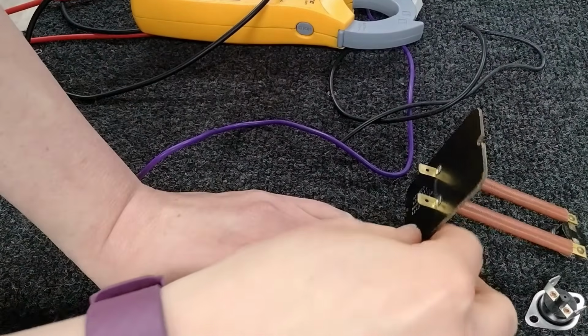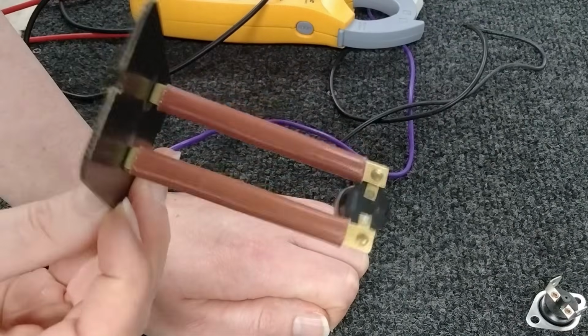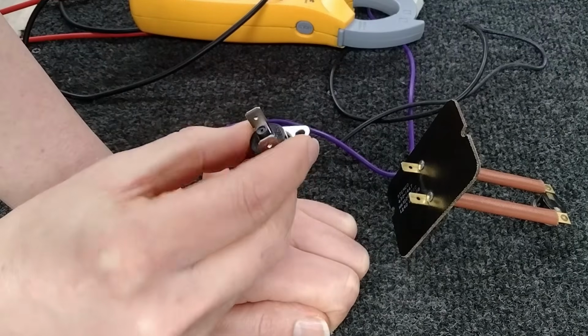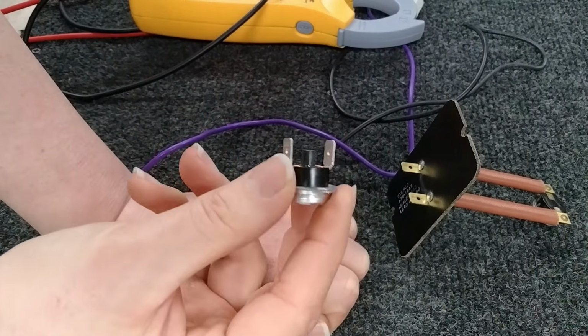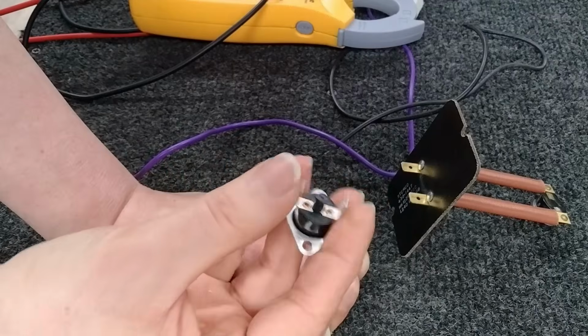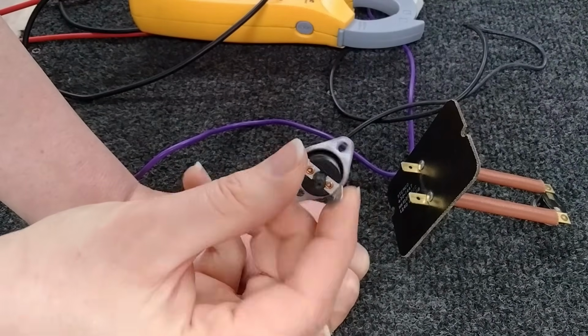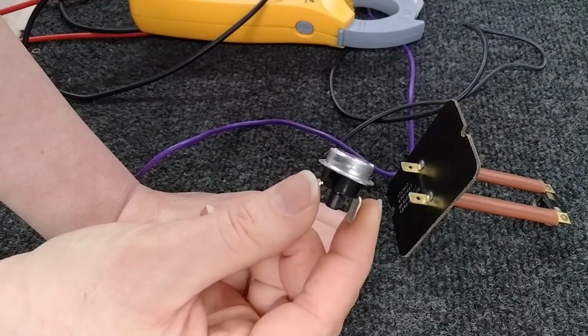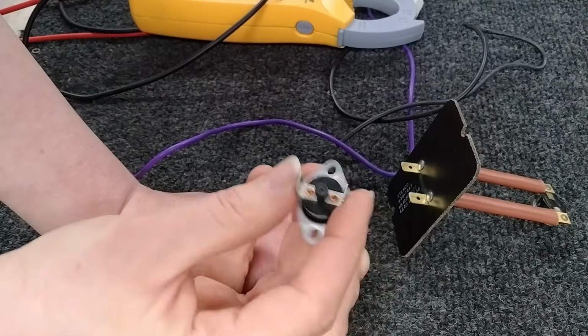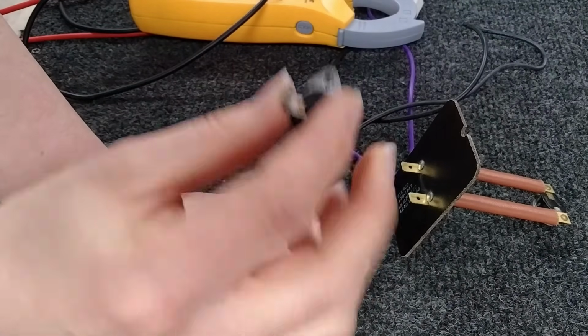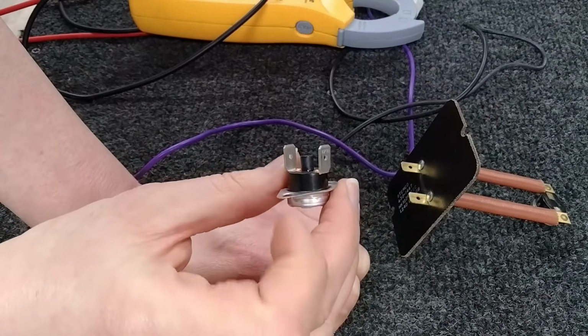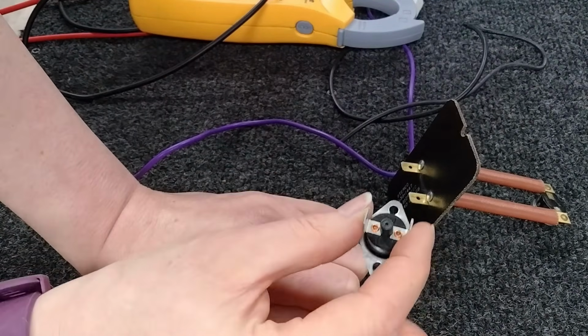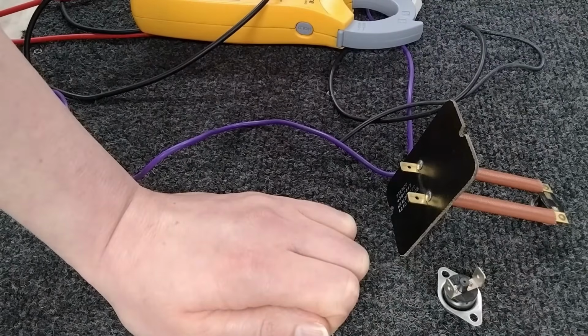That gives you an idea of things you need to look for, the functionality of these limits, and how they work. And these little guys here, your rollout switches, when they pop like that, if you do replace them, and guess what, the new one does the same thing, then again, that's probably an indication that they are doing their job and it's overheating. Whether that be flame rollout, which is bad, means it's time to get a new heat exchanger.